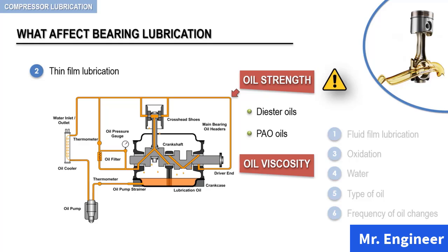Keep in mind that only thin films of oil exist at points of frictional contact in anti-friction bearings. So, to minimize metal-to-metal contact and to reduce friction, a lubricating oil having adequate film strength is required. Cooling, cleaning, and protection against rusting are also important functions of the lubricating oil. And again, the oil viscosity should be in a range that provides ready distribution.